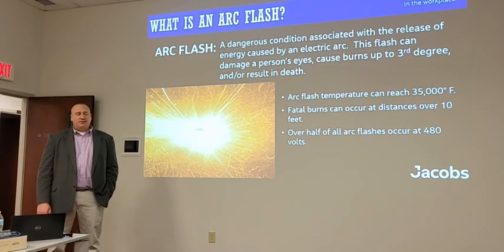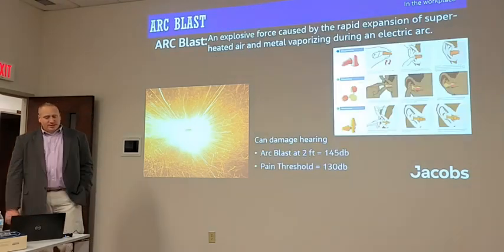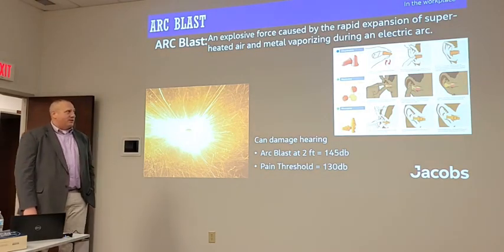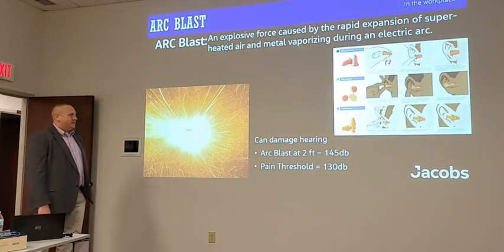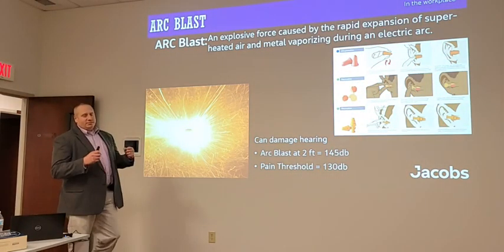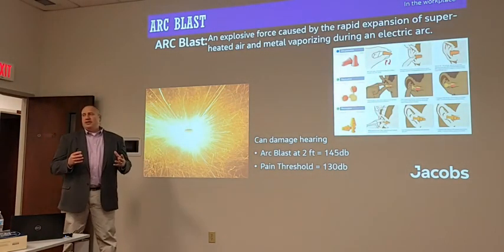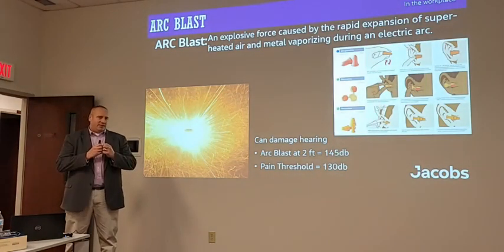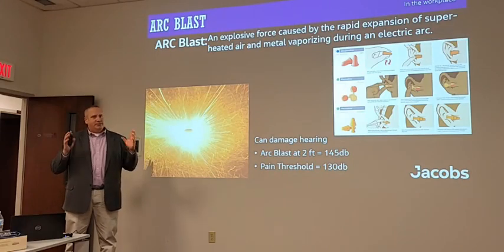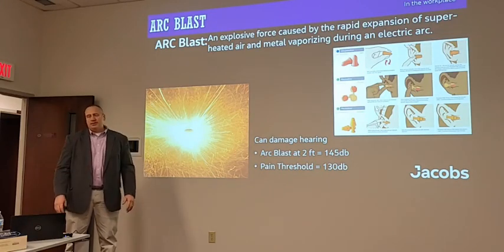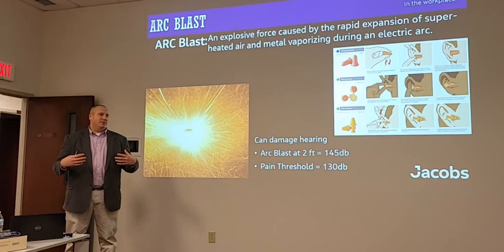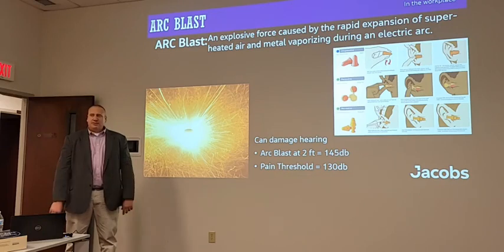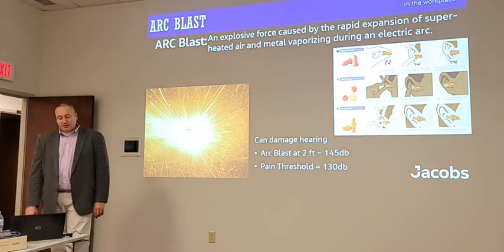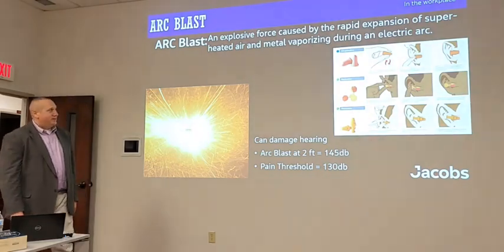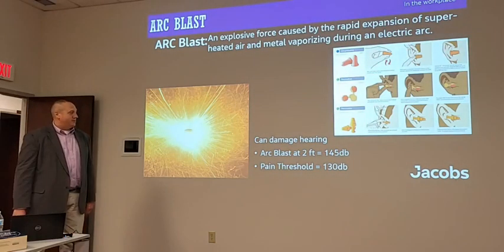Then you also have the arc blast. When you're talking about the temperatures and the rapid expansion of air, most of your arc flash in industry is going to happen inside an enclosure, and all of that rapid expansion wants to get out somewhere. It forces its way, typically right towards the worker, out of the front of the enclosure in a pressure wave that is commonly called the arc blast. And it can blow doors off of enclosures.